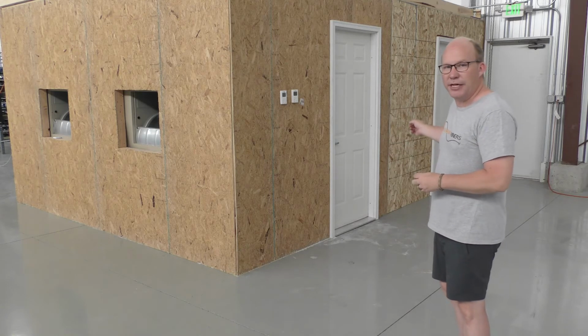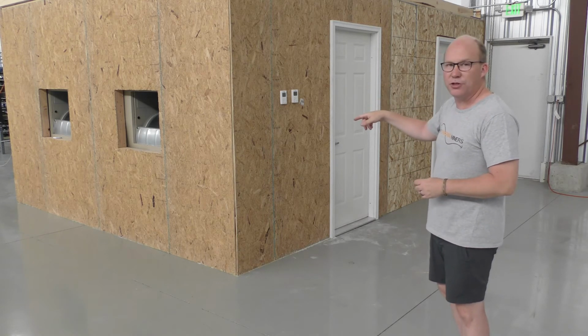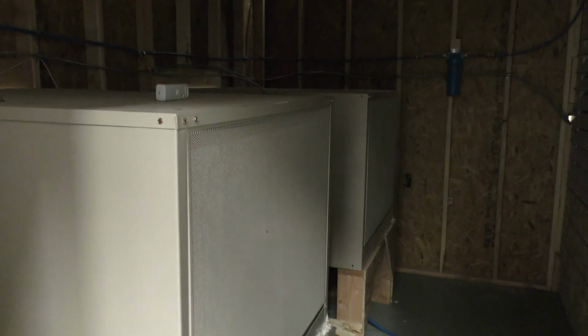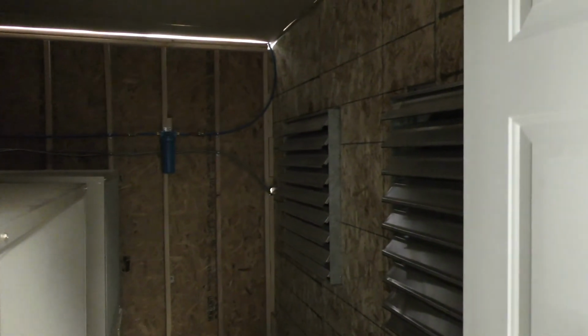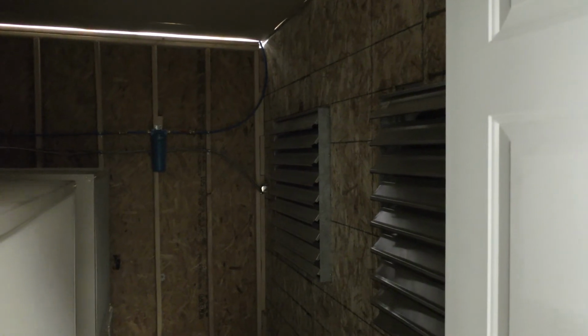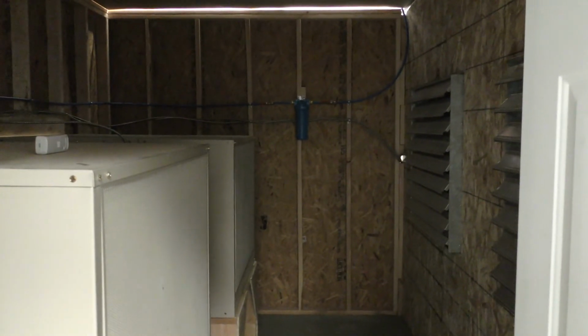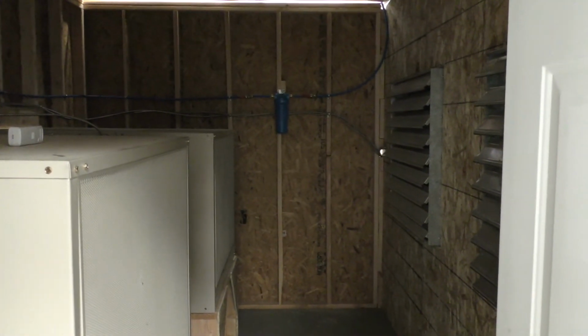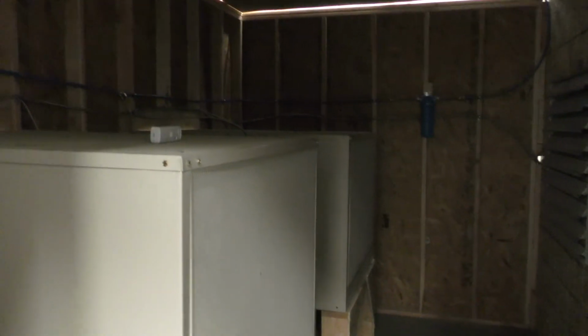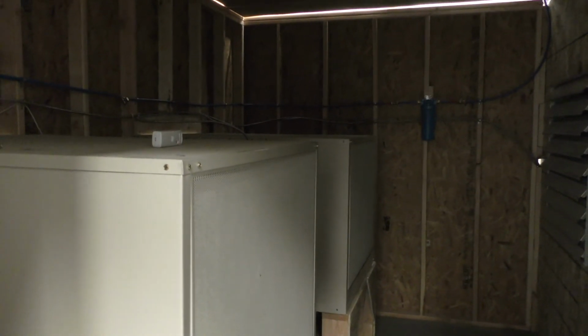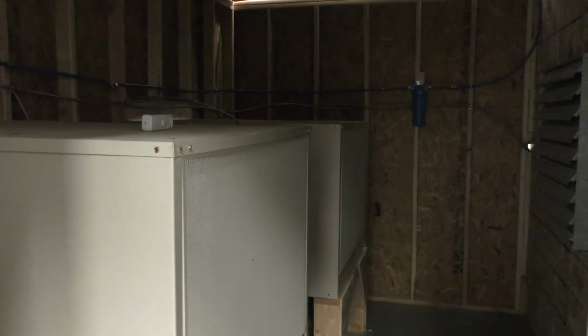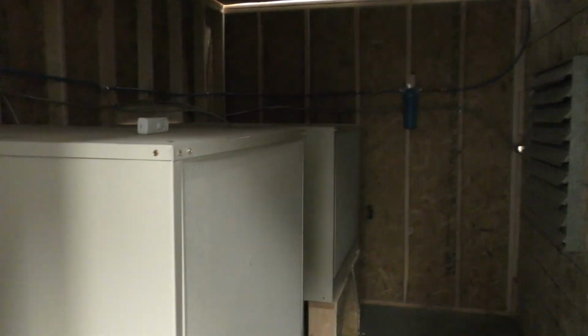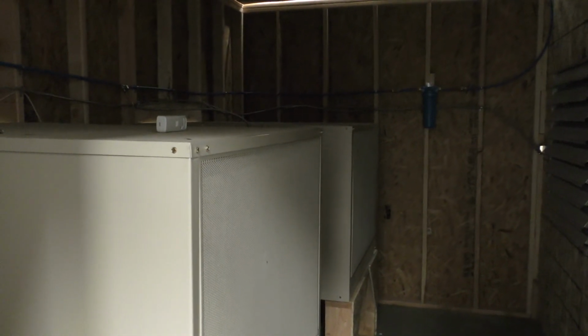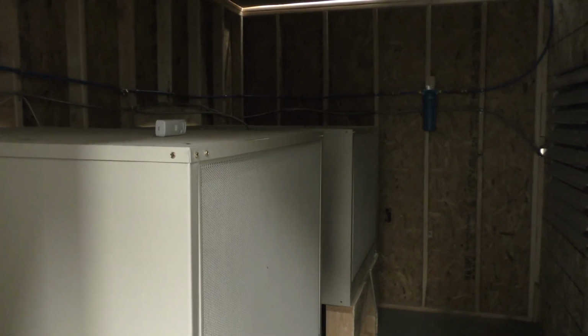The second door here is where our evaporative coolers are. You can see them running here, pulling air. There's actually on this wall, behind those air filters, 2 fans. Those fans just help pull air through the air filters so that the evaporative coolers don't have to pull as hard to get the air through there. We have a water filter down there on the end to filter some of the water before it gets into the evaporative coolers as well.